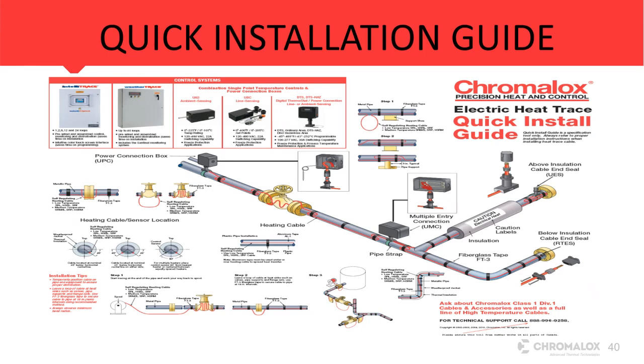Talking about end seals, one of the things I didn't mention on the other side is that if we have an end seal that's underneath the insulation and I don't have any isometric drawings, I don't know where the circuit starts and stops. And I'm relying on maybe a gentleman or a lady that's been working at the plant for a number of years, and this person knows all of the heat tracing, where it all starts and stops. Well, if that person retires or moves on, we have no idea of where the heat tracing starts and stops. How do we go about troubleshooting it? So that's why, to me, it's important to get those isometrics and have those isometrics, even if it's for 1 or 2 circuits, to go back and be able to troubleshoot and add. It just makes it so much easier whenever you're trying to do some basic troubleshooting.